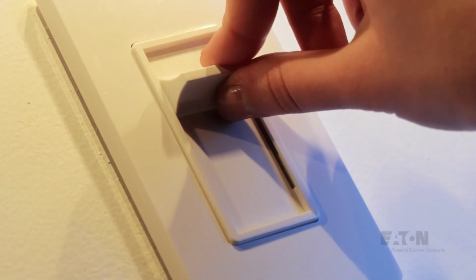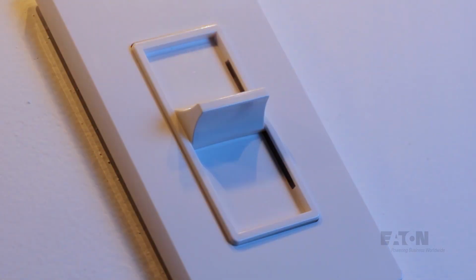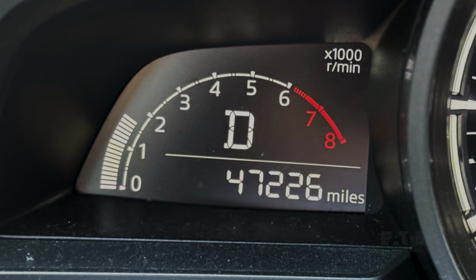Using the light dimmer analogy, you could change the light from off to any output level and then leave it there without going to full output power. With the vehicle analogy, you could slowly adjust your speed from a stop to any speed and then stay there, and beyond that, you could readjust your speed or even slow down to a stop. Controlling the starting, stopping, and running of a motor are completely adjustable with a variable frequency drive.